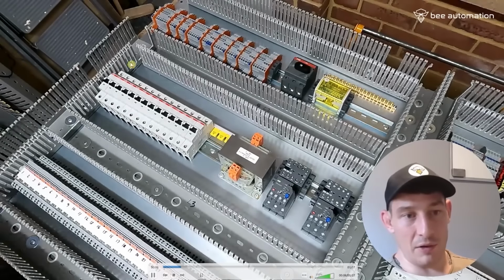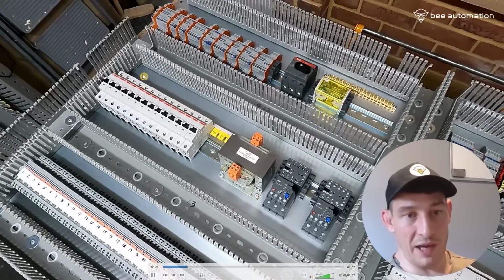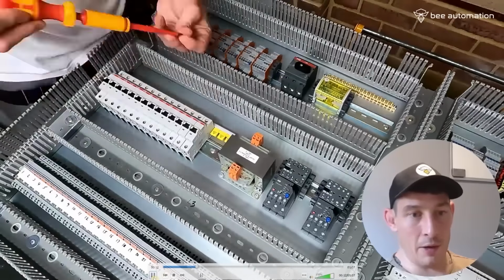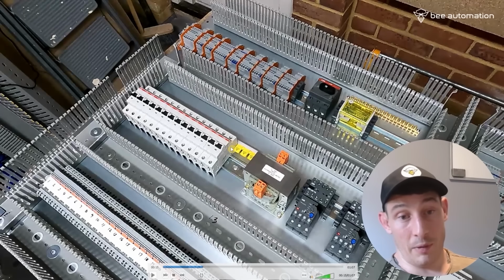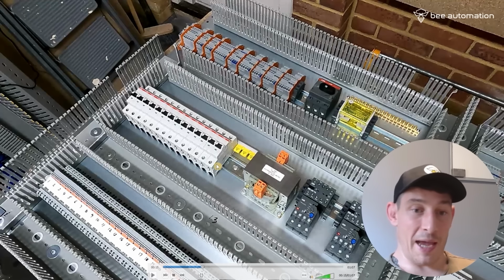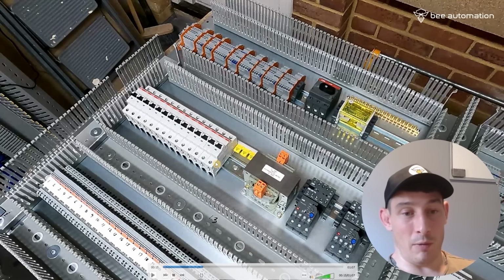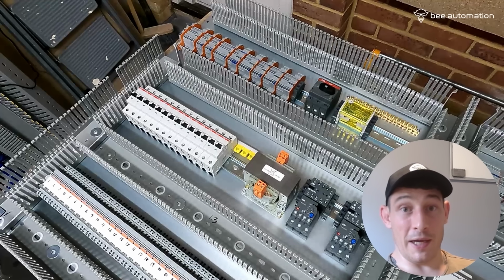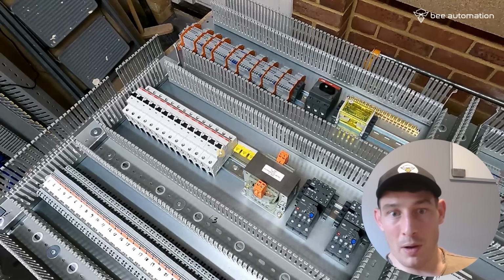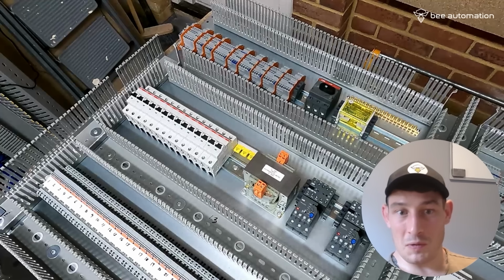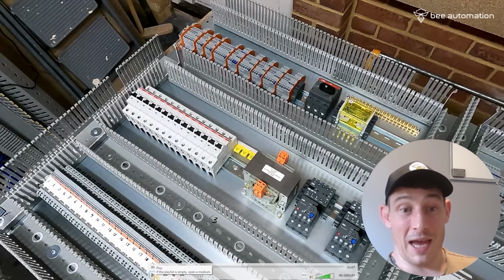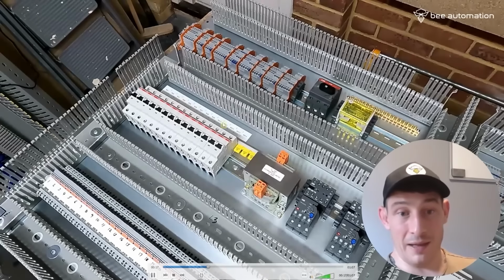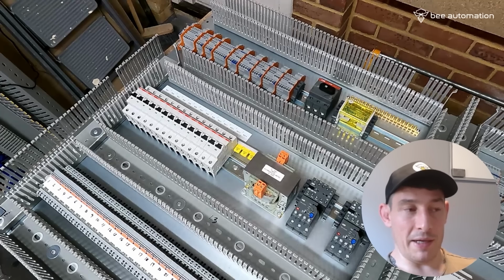Next thing I do is the MCBs, and you saw there with a tape measure, working out the length. For these ones, rather than sticking the label on the actual MCB, I'm going to stick it on the back plate. The reason being MCBs are pretty much fixed, they don't move about within the panel, but they're things with a higher likelihood of being changed, swapped out, burnt out, or maybe you need to increase or decrease the size. So to save anyone having to redo that, I'm sticking the labels to the back plate, and then no one has to worry about relabeling an MCB when they switch it in or out.